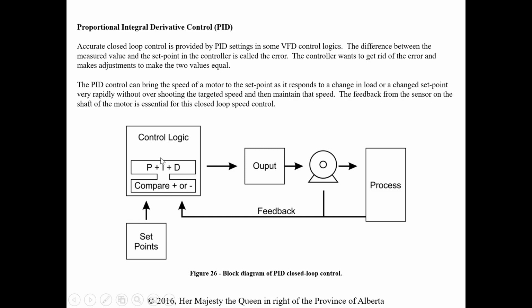So the PID control can bring the speed of a motor to its set point as it responds to a change in load or a change in set point very rapidly, without overshooting the targeted speed, and then maintain that speed. So it gives us very specific speed control. But again, we're adding a lot more to this. It's going to be a lot more specific, but a lot more costly and a lot more involved. The feedback from the sensor on the motor shaft is essential for this closed loop because it needs to know exactly how fast it's going.